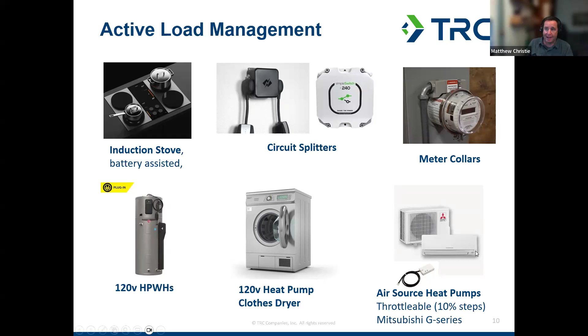So there's two different flavors of this. One is I added them all up and they don't add up to 80, but I don't have enough breaker spaces in my panel. I've run out of space, I don't have enough slots. That's allowed, you just put on a sub panel. So if you need a whole bunch, like a handful of breaker spaces, add a sub panel. Basically this is just an appendage, extra slots that you can add on.